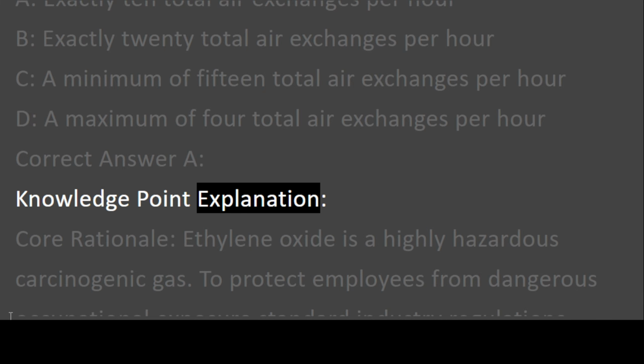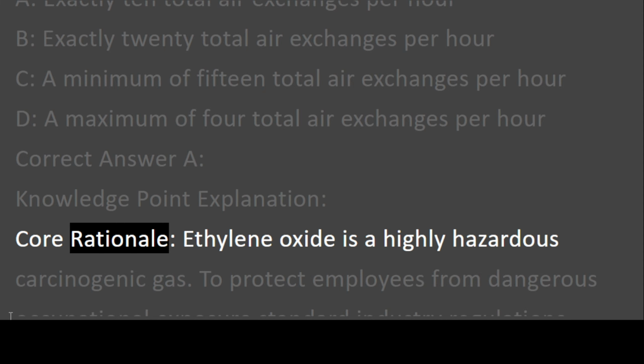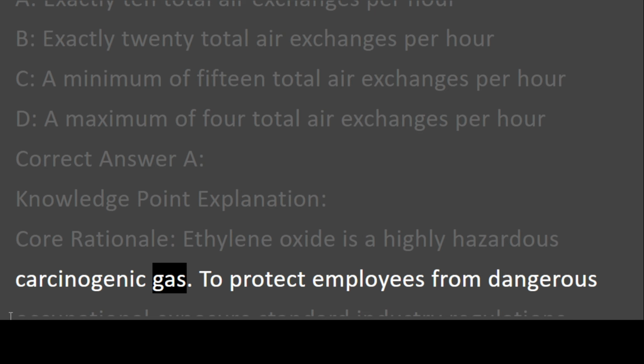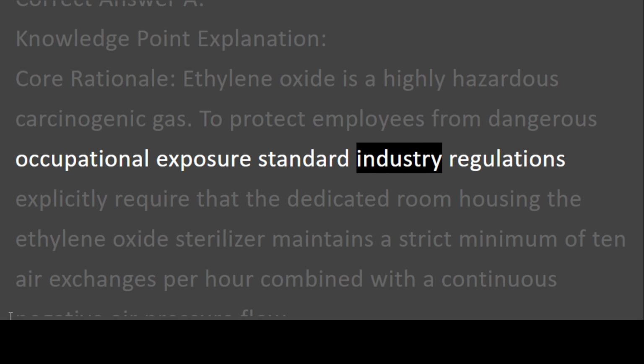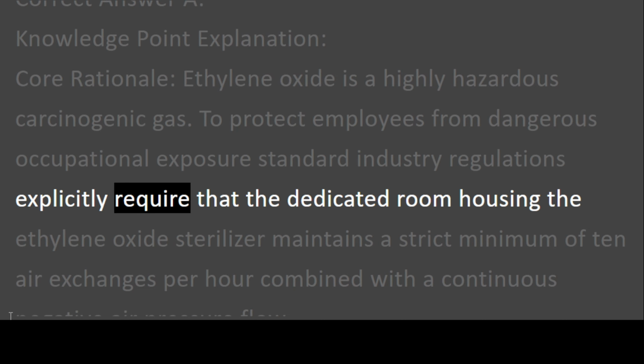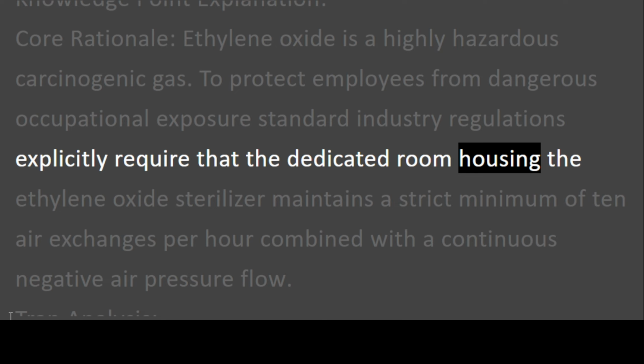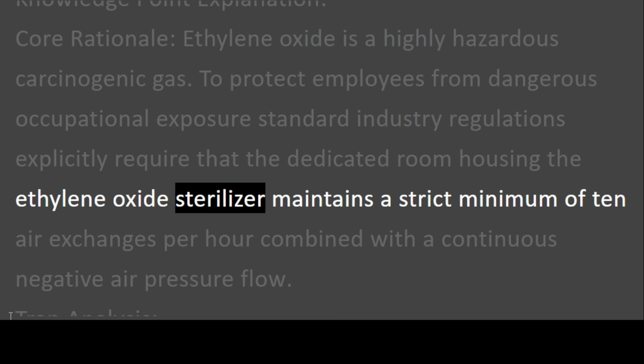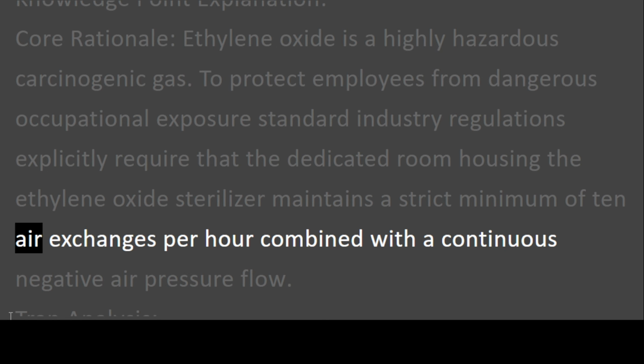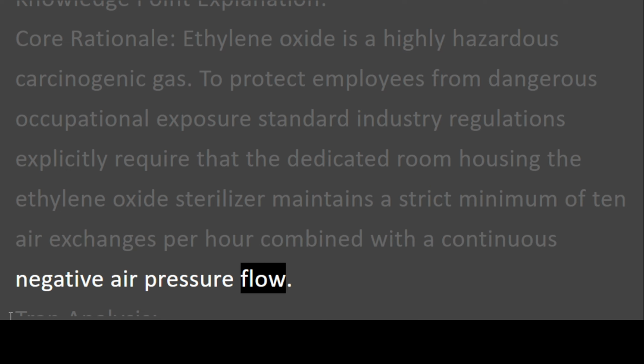Knowledge point explanation. Core rationale: ethylene oxide is a highly hazardous carcinogenic gas. To protect employees from dangerous occupational exposure, standard industry regulations explicitly require that the dedicated room housing the ethylene oxide sterilizer maintains a strict minimum of 10 air exchanges per hour combined with a continuous negative air pressure flow.